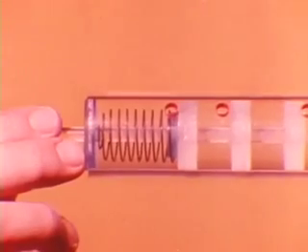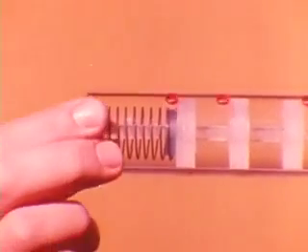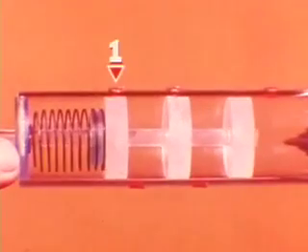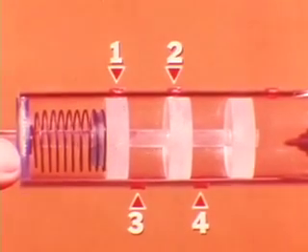The spool valve may be operated manually, for example, against a spring. Here, ports one and two are blocked by the lands as ports three and four are open to oil pressure. Moving the spool valve against the spring opens ports one and two, allowing simultaneous oil flow across the valve through both ports.